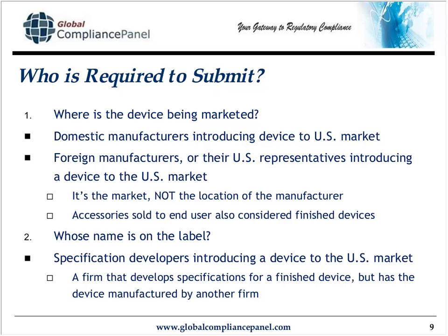Remember, just in the back of your minds when you're evaluating whether you need to submit a 510K, any accessories that can be sold directly to the end user are also considered finished devices. So if they can be used by themselves, then they are considered finished devices.